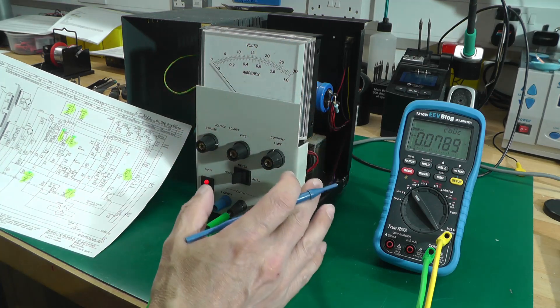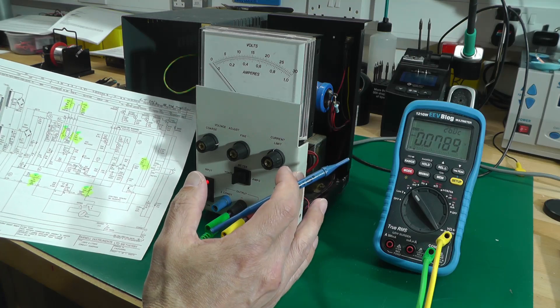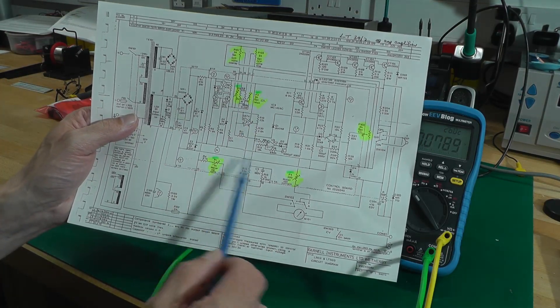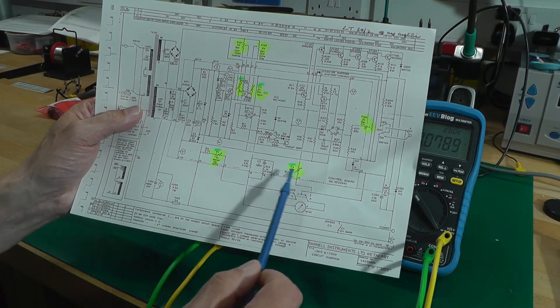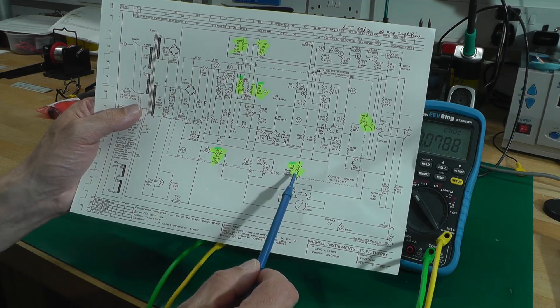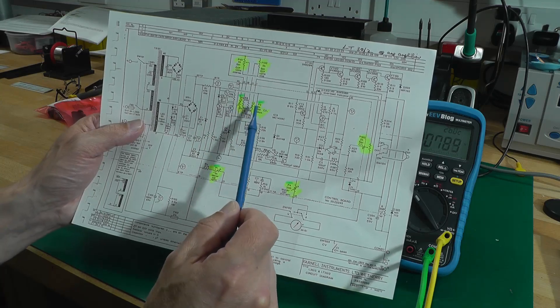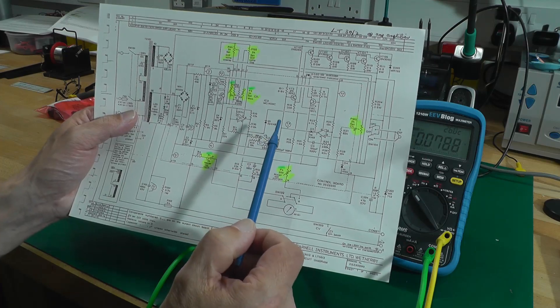I don't really have the proper manual for this unit. I've got a calibration manual but unfortunately it's for the fully transistorized version, not the op-amp version I've got here. We're just going to wing it. You've got four potentiometers on the circuit board itself: two for setting the full scale of the meter depending whether they're in voltage mode or current mode, and two potentiometers for adjusting the span of the output voltage. There are no zero pots on this power supply at all.